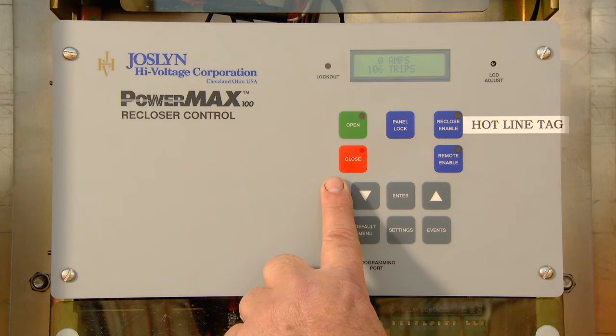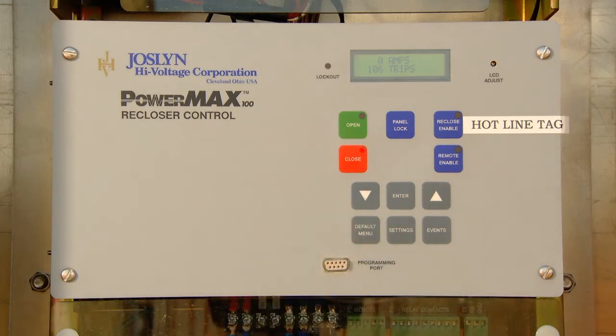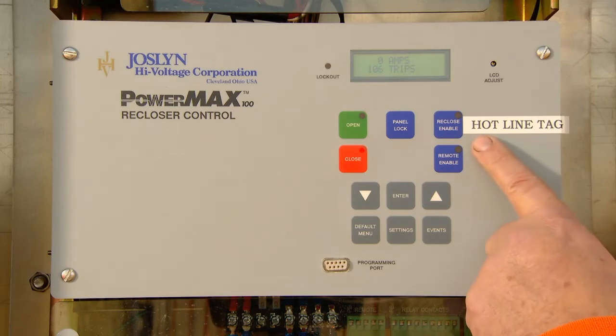There is an intentional blocking between manual closing operations of approximately 5 seconds to prevent excessive duty on the control. This delay has no effect and does not limit reclosing operations. Both the open and close LEDs will be illuminated at the same time when the recloser is not connected to the control. Next, in the older controls, we have Reclose Enable, which is also your hotline tag feature.